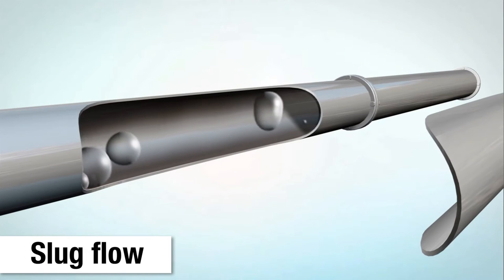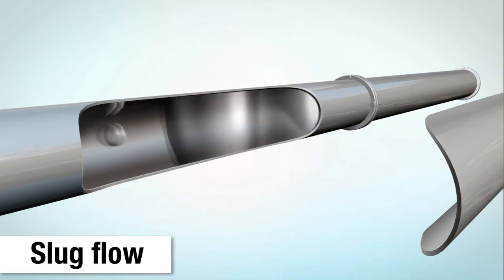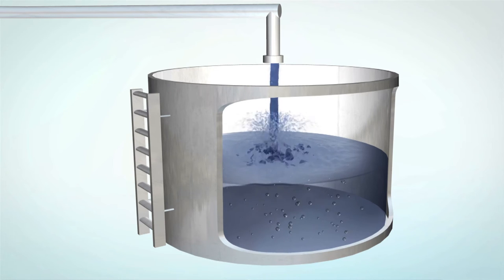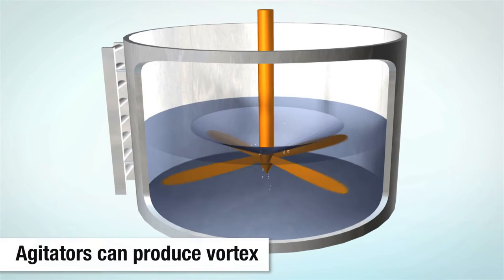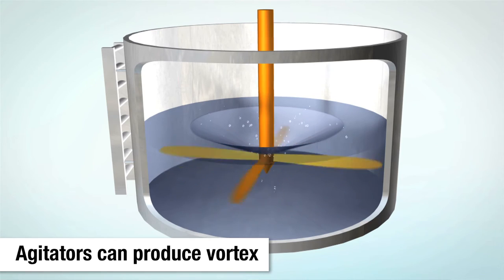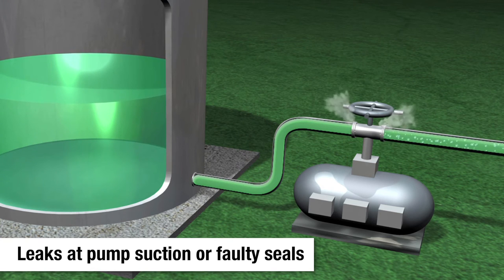Slug flow is usually unintentional and can occur as a result of a process upset in tank farm and oil well applications, where there are periodic, coalesced bubbles. Slug flow can occur as a result of long drops into tanks, where splashing occurs when the stream enters the liquid. The farther the liquid falls, the more air is entrained. Agitators can produce a vortex that entrains air into a liquid, especially when tank levels are low. Leaks on the suction side of pumps or in the pump seals themselves can also introduce air into a pipeline.